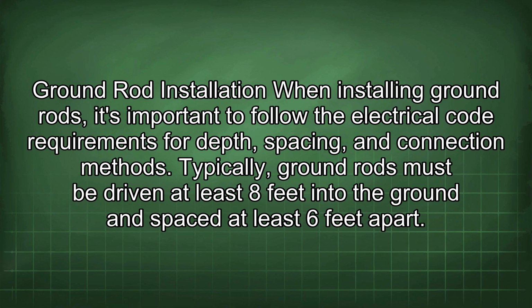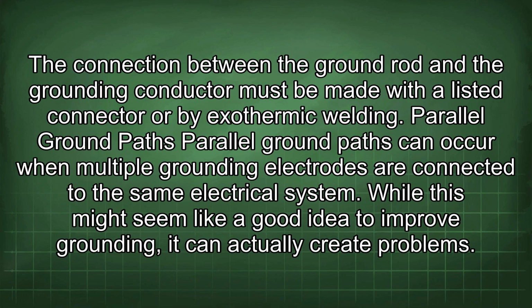Ground rod installation. When installing ground rods, it's important to follow the electrical code requirements for depth, spacing, and connection methods. Typically, ground rods must be driven at least 8 feet into the ground and spaced at least 6 feet apart. The connection between the ground rod and the grounding conductor must be made with a listed connector or by exothermic welding.